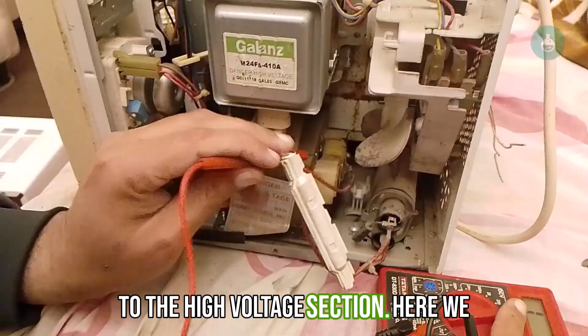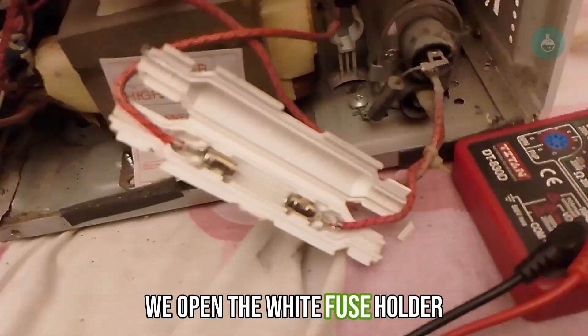Now we move to the high voltage section. Here we can see the transformer. Near the transformer, there is another fuse, inside a white protective case. This is the high voltage fuse. We open the white fuse holder carefully and remove the fuse from the case.